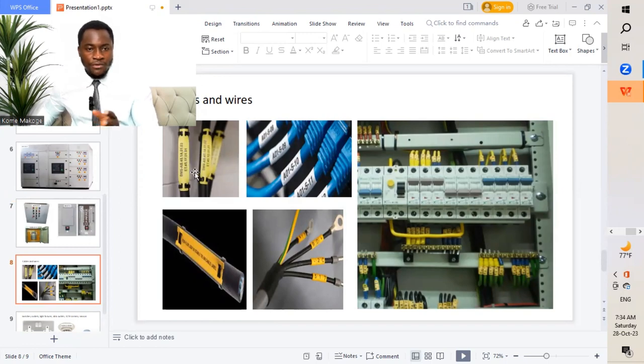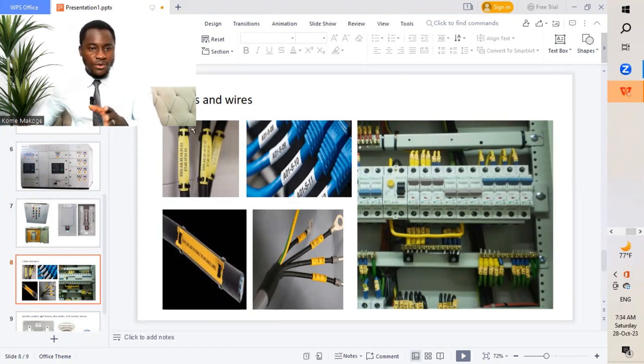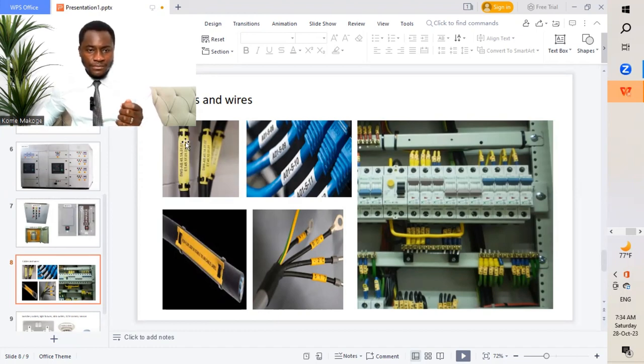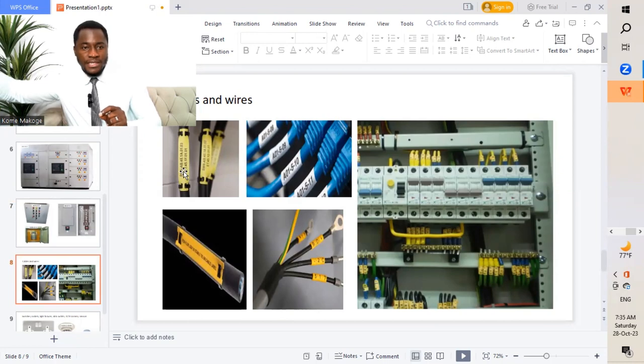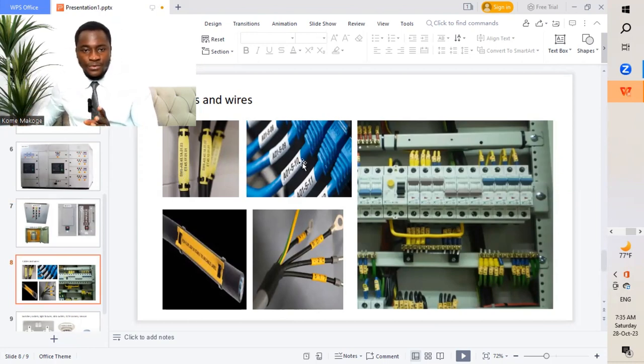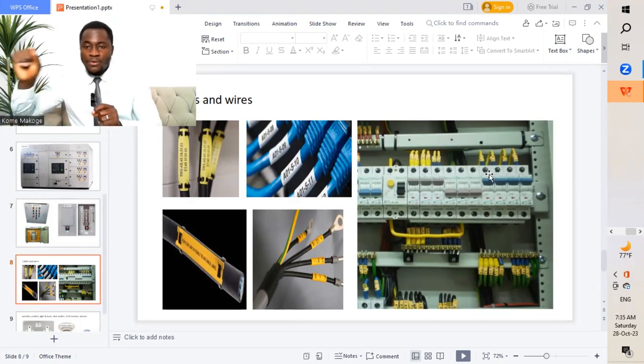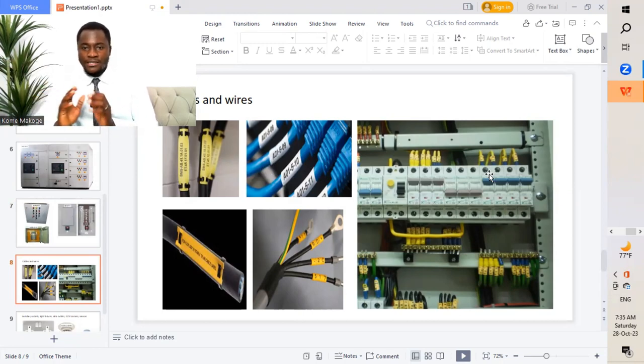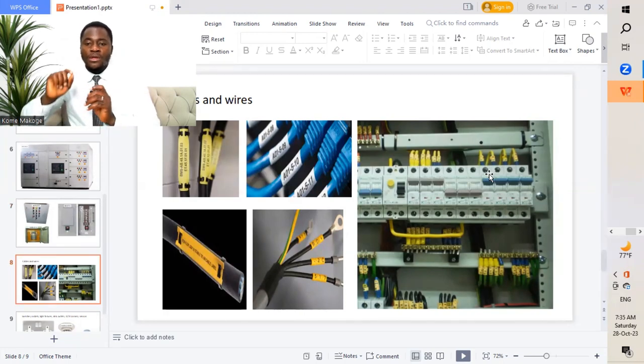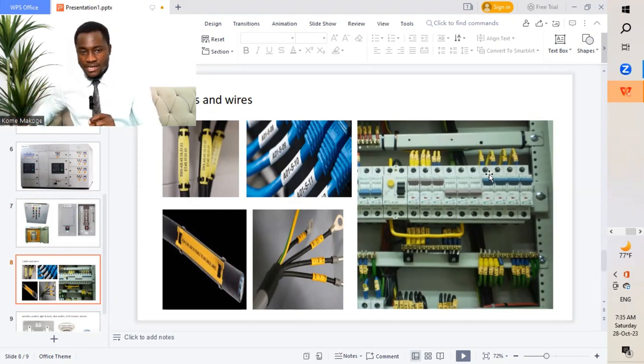We'll see identifications as such for cables — talking of probably armored cables or PVC three-core cables. We are going to place the labeling as such. It varies with different projects. We'll place them and put certain writings on them, so we get to understand these cables have been installed running from this end going to this other end. We'll have our data cables, which are already patched, and then we have our wires installed inside our distribution board or SMDBs. We'll have different labelings so we get to understand where it's coming from and where it's going to. This is very important — during maintenance, we know our cables or wires have been installed running from this location to this other location, which eases maintenance as well as installation works.